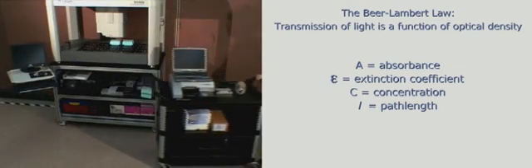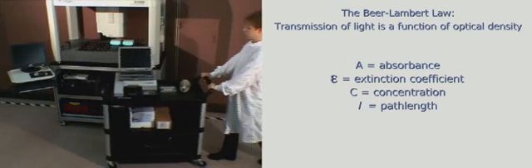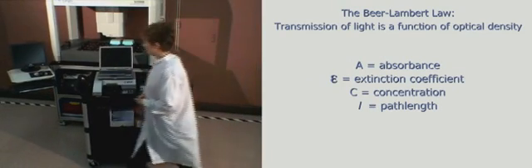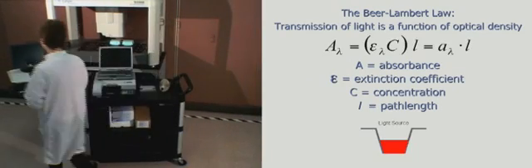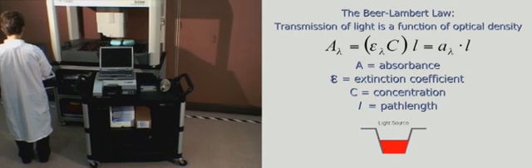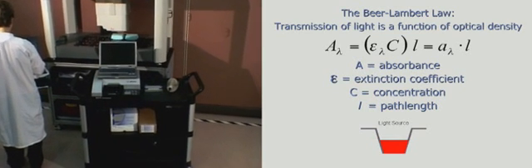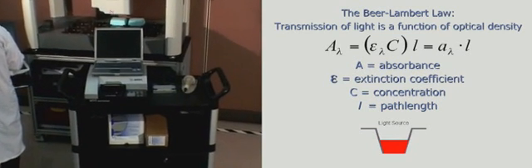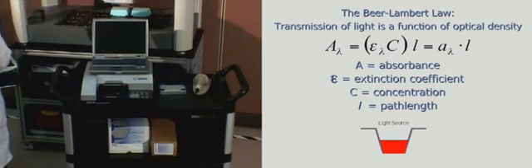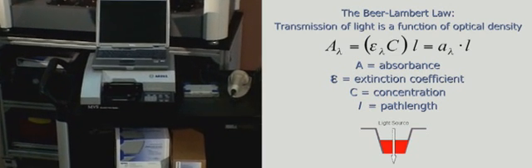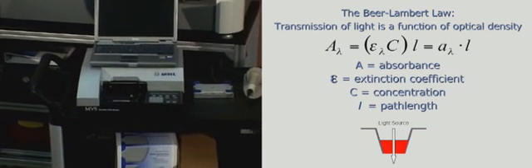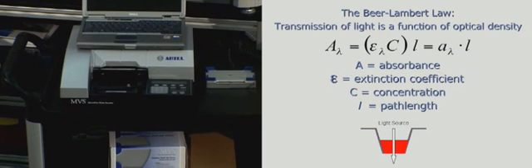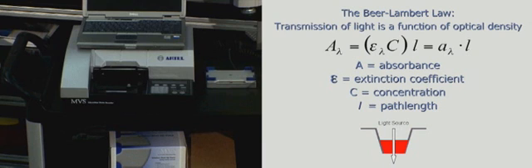The scientific foundation for the MVS is the Beer-Lambert Law, which states that transmission of light through a liquid is directly related to the optical density of the liquid. Absorbance photometry is the basis for myriad analytical systems in use in laboratories. In its simplest form, it is also the foundation for some of the methods traditionally used to verify liquid delivery performance of both manual pipettes and automated liquid delivery instruments.